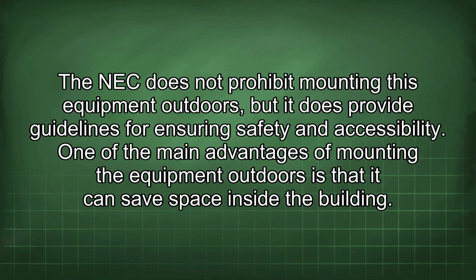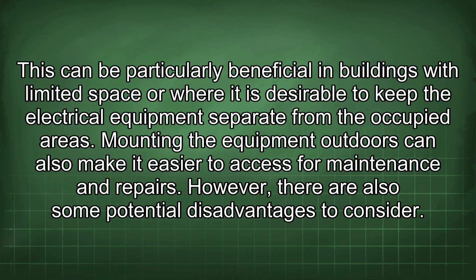The NEC does not prohibit mounting this equipment outdoors, but it does provide guidelines for ensuring safety and accessibility. One of the main advantages of mounting the equipment outdoors is that it can save space inside the building. This can be particularly beneficial in buildings with limited space or where it is desirable to keep the electrical equipment separate from the occupied areas. Mounting the equipment outdoors can also make it easier to access for maintenance and repairs.